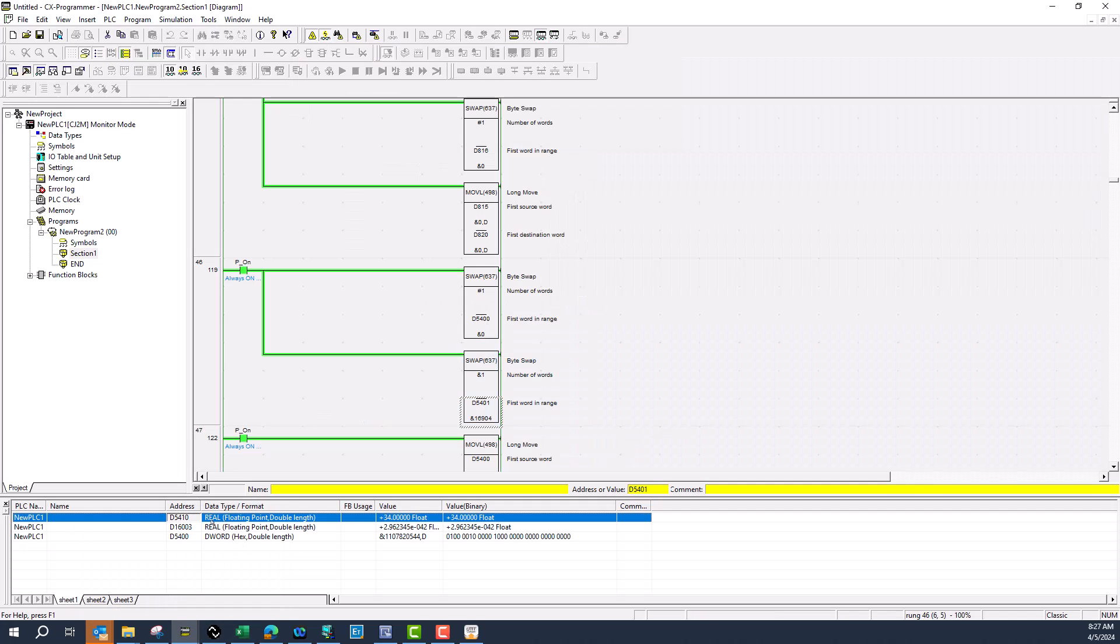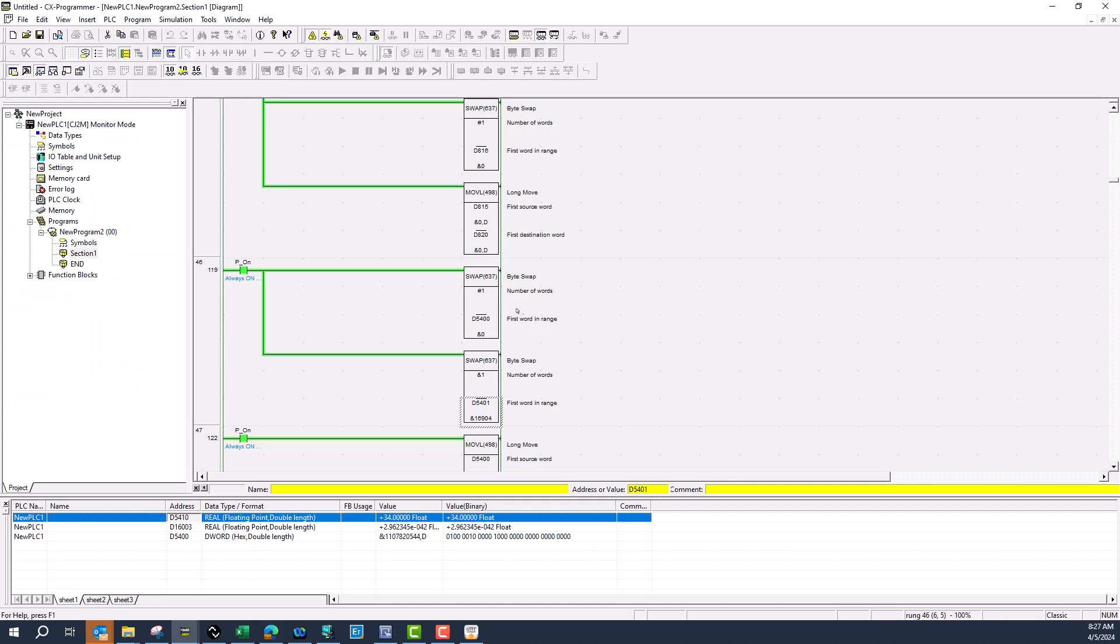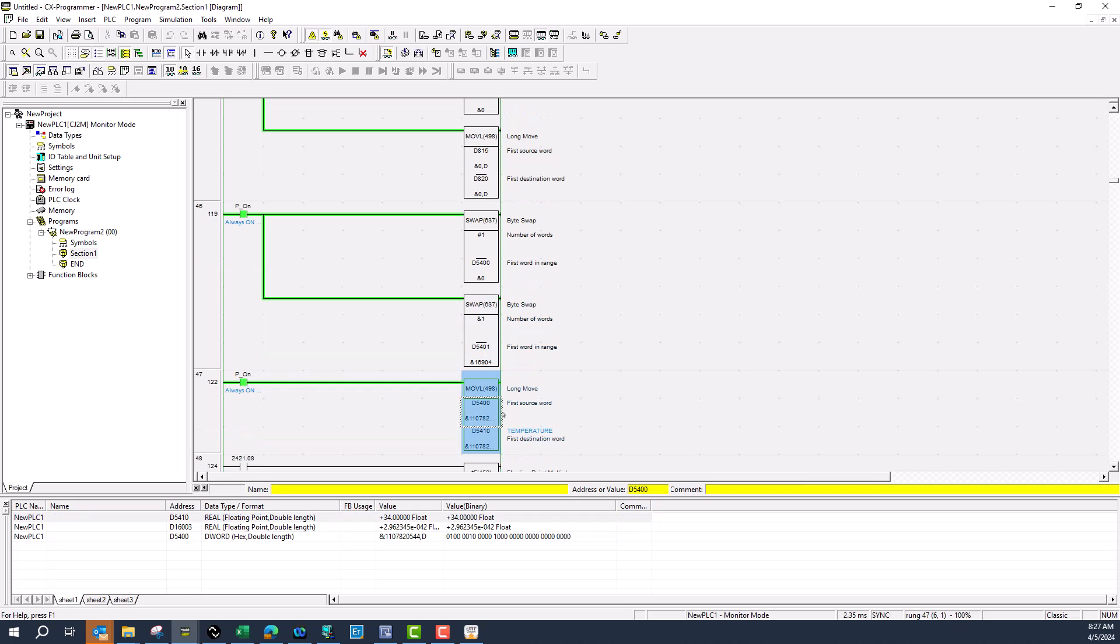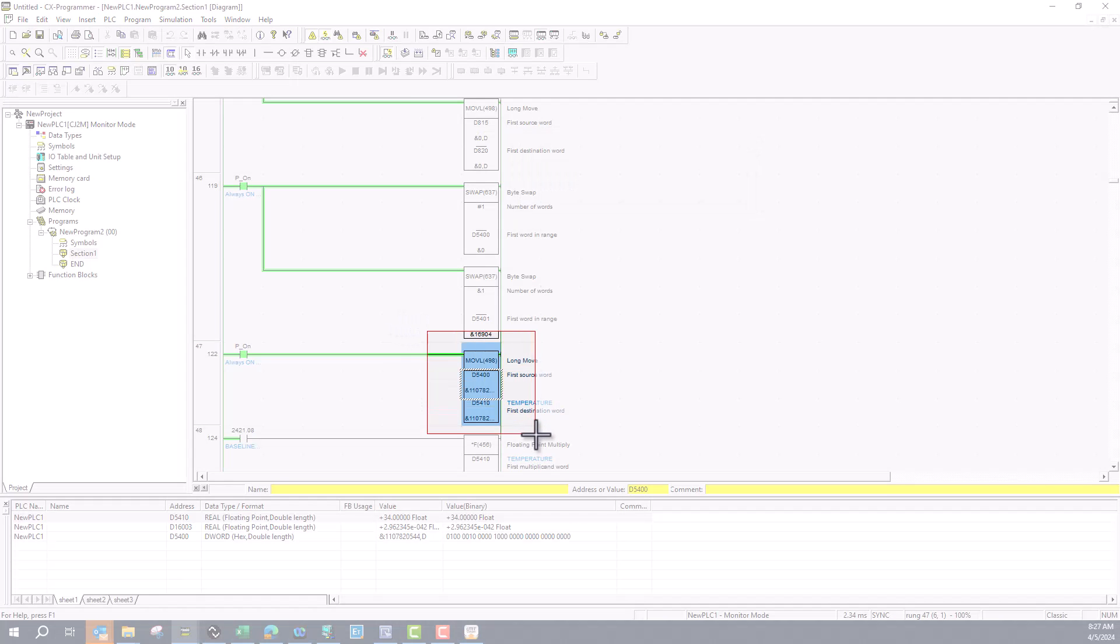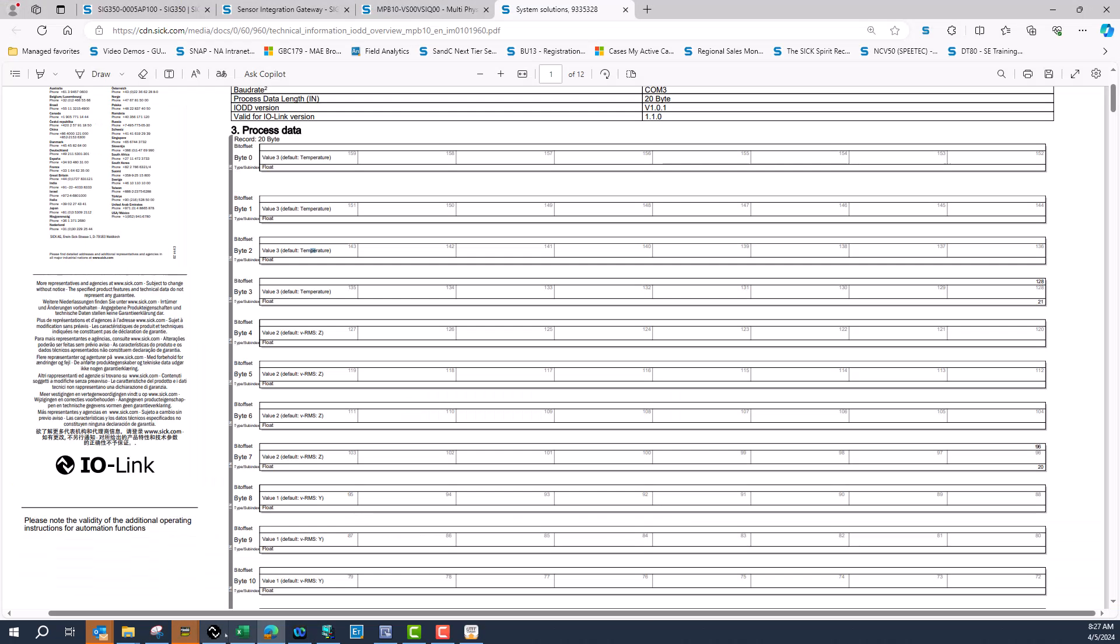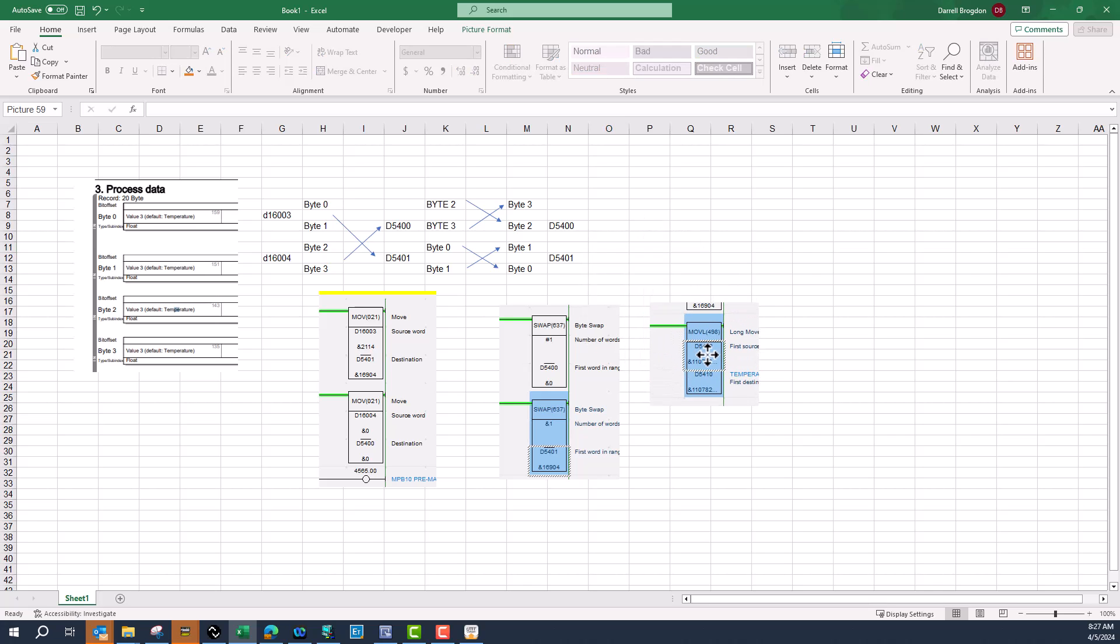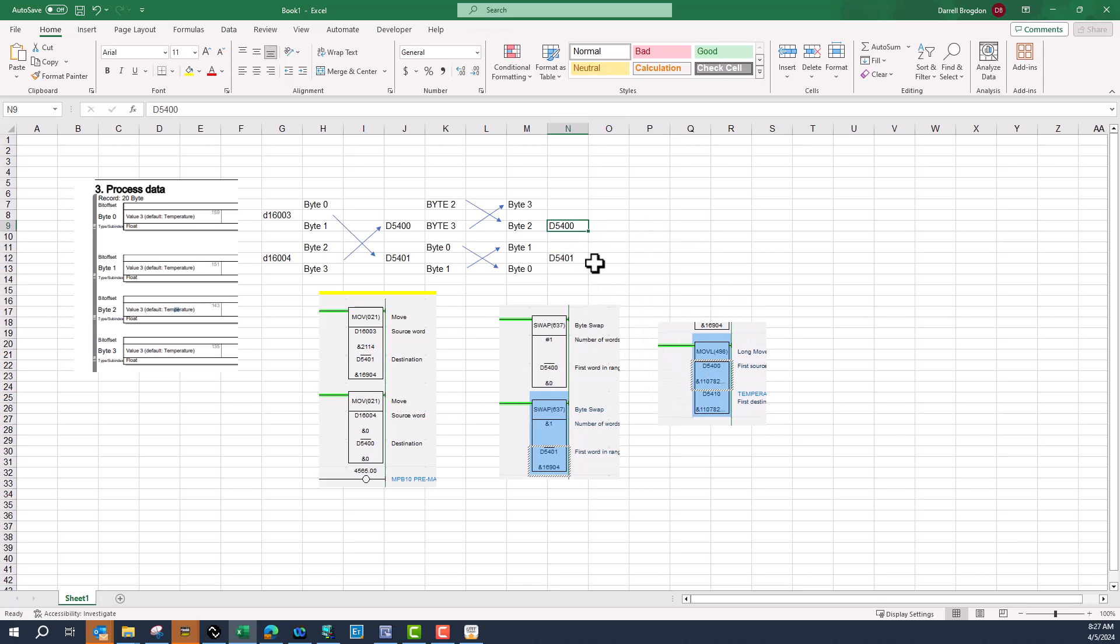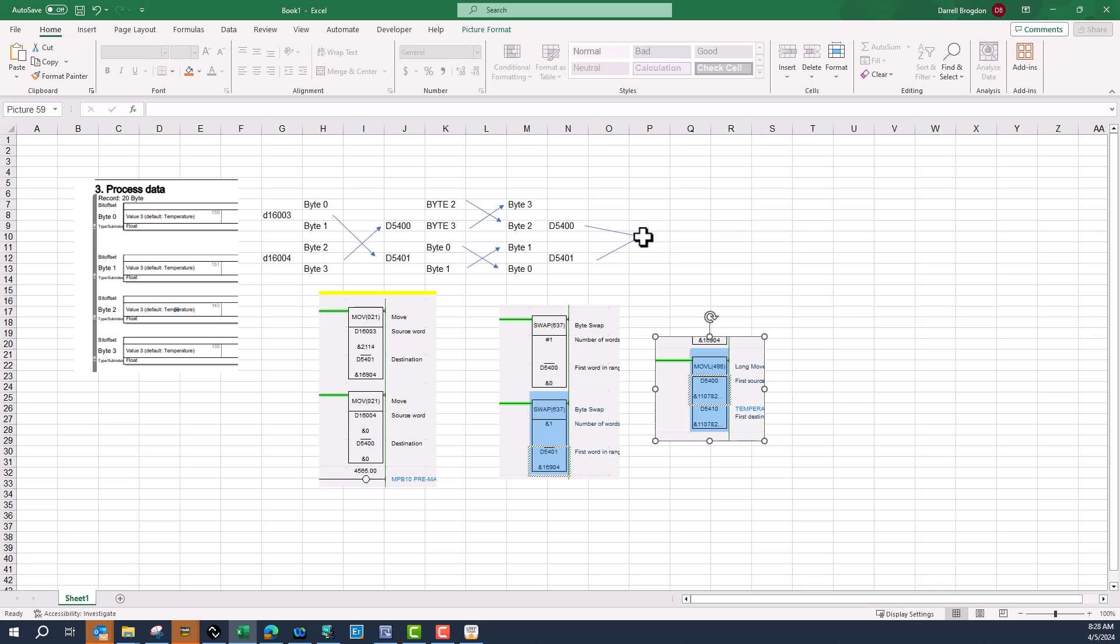As you see here, 5400 and 5401, what I did is a move L. This is how I put those together. So I did a byte swap, then I did a word swap. Now I'm using it for a double word. That is my next instruction in the PLC. I'm taking these two and turning them into one word, but it's a double word, and I'm pushing those into d5410.